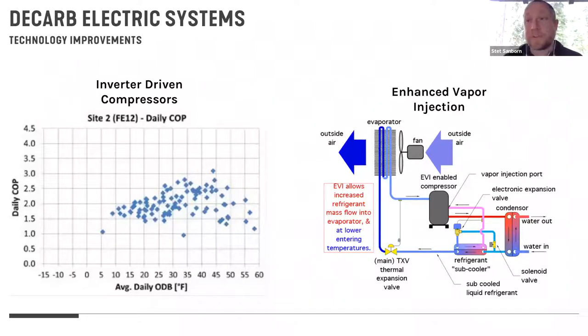The two driving technology changes that we see in the heat pump market for cold climates: first, almost universally, the industry is moving to inverter-driven compressors, which has benefits in non-cold climates as well. But the ability to match the compressor frequency and effort of the compressor to the load and outside air temperature is incredibly important in order to maintain that coefficient of performance down into low ambient temperatures.